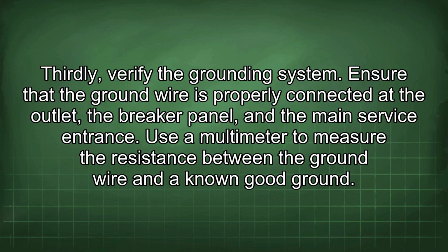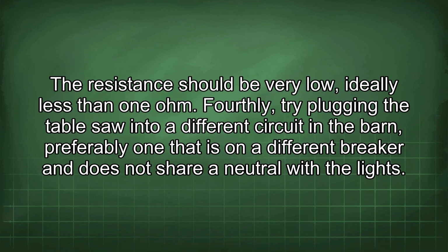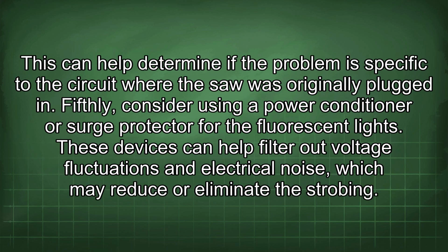Thirdly, verify the grounding system. Ensure that the ground wire is properly connected at the outlet, the breaker panel, and the main service entrance. Use a multimeter to measure the resistance between the ground wire and a known good ground. The resistance should be very low, ideally less than 1 ohm. Fourthly, try plugging the table saw into a different circuit in the barn, preferably one that is on a different breaker and does not share a neutral with the lights. This can help determine if the problem is specific to the circuit where the saw was originally plugged in.